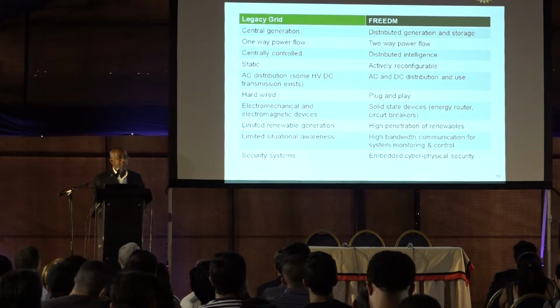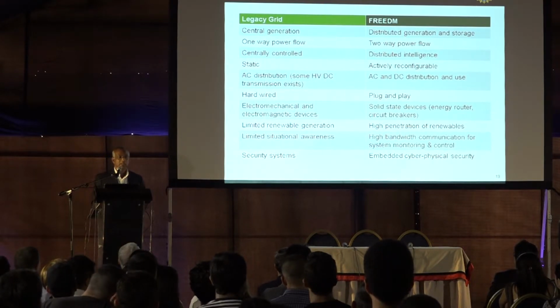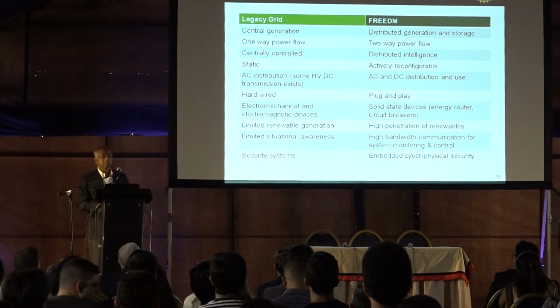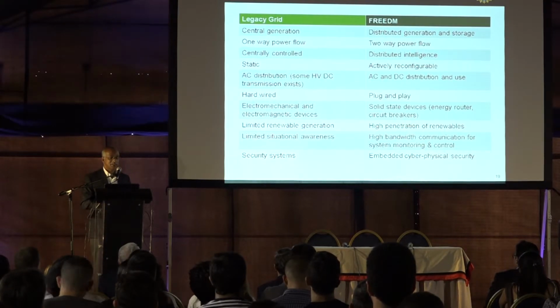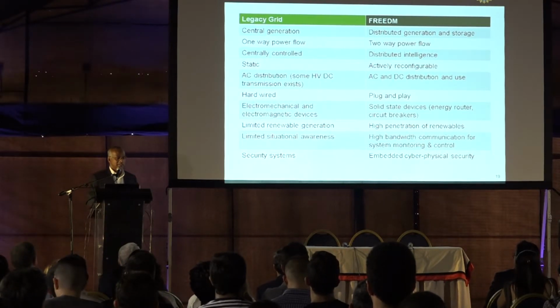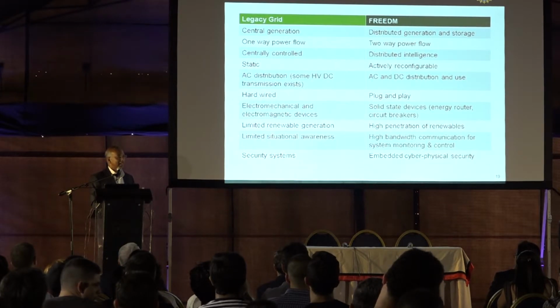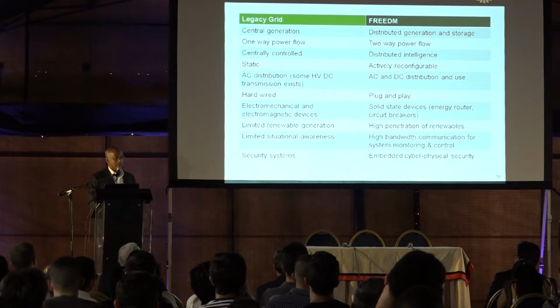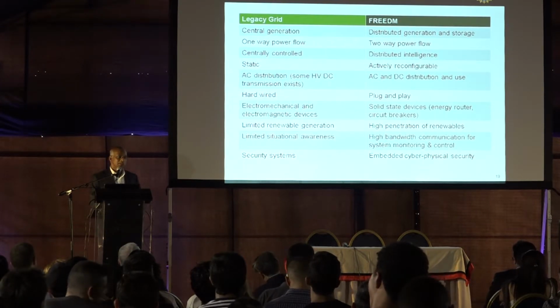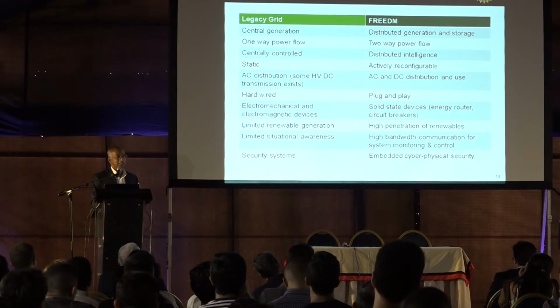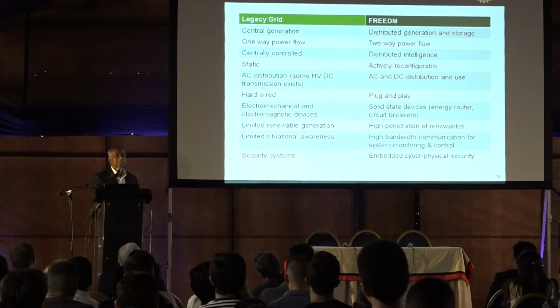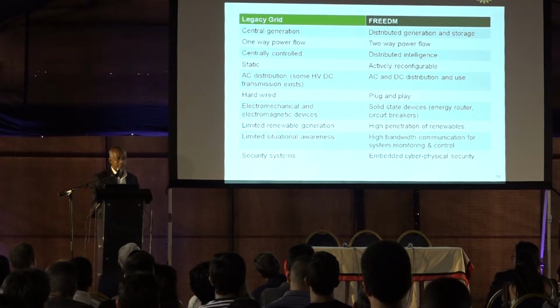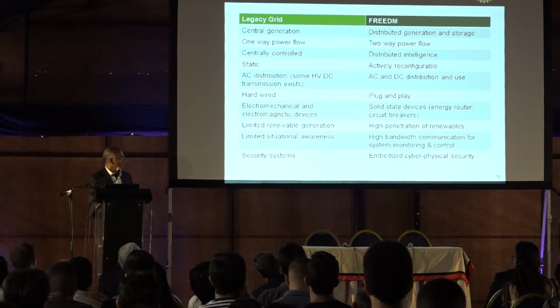So the concept is like the traditional grid, or the legacy grid. The way it's developed is based on the things that I was mentioning: centralized generation, one-way power flow. It's a static system. It's an AC-based system. It's a hardwired system, and there is limited opportunity to introduce renewables because you cannot just add on to the existing system without disrupting its stability or performance. So those things need to be carefully evaluated. And then the security systems are also ad hoc.